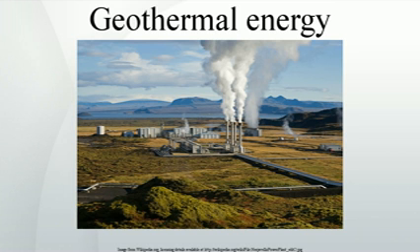Direct heating applications can use much shallower wells with lower temperatures, so smaller systems with lower costs and risks are feasible. Residential geothermal heat pumps with a capacity of 10 kilowatt are routinely installed for around $1 to $3,000 per kilowatt. District heating systems may benefit from economies of scale if demand is geographically dense, as in cities and greenhouses, but otherwise piping installation dominates capital costs.